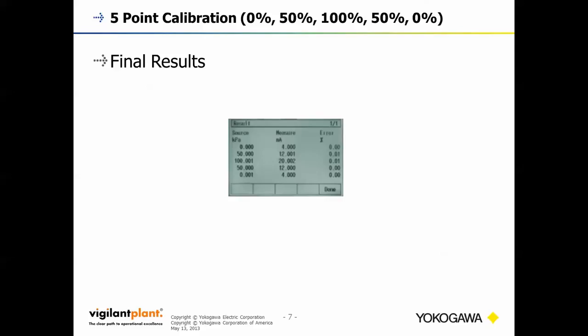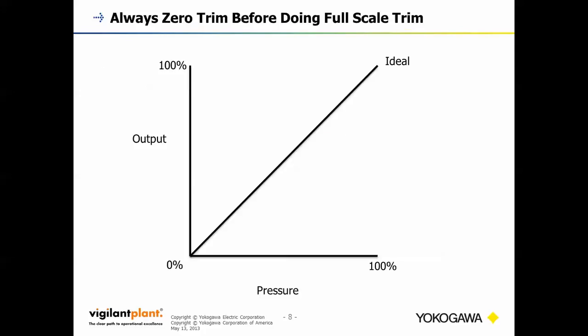But if it was out of tolerance, we're going to go over and show you how with Fieldmate you can trim the transmitter and get it back into tolerance if your error was outside of tolerance. So when you're trimming a transmitter, I just wanted to go over a general practice. The main takeaway from this is always do a 0 trim before doing a full scale trim, and this little diagram will kind of explain that.